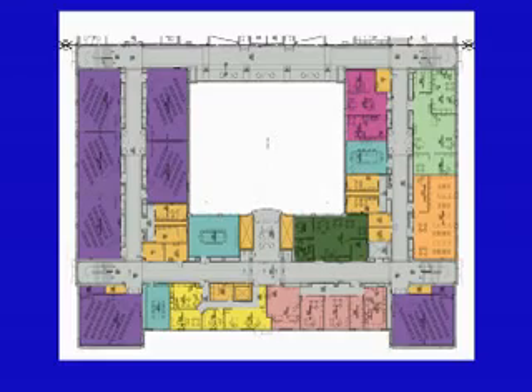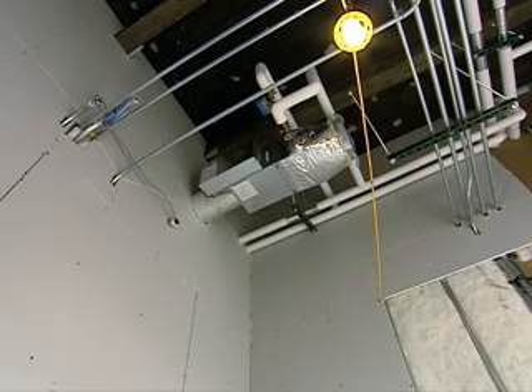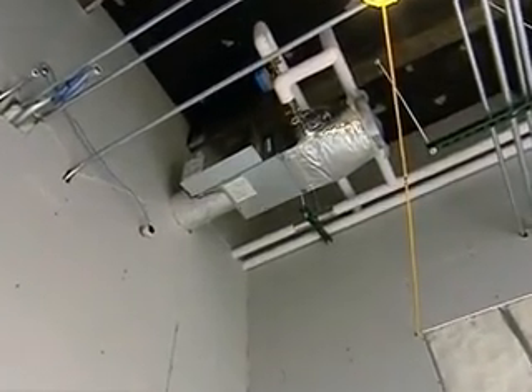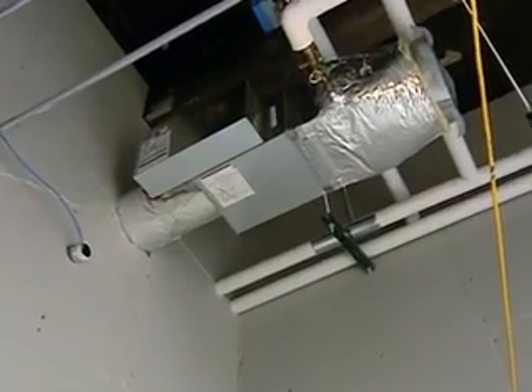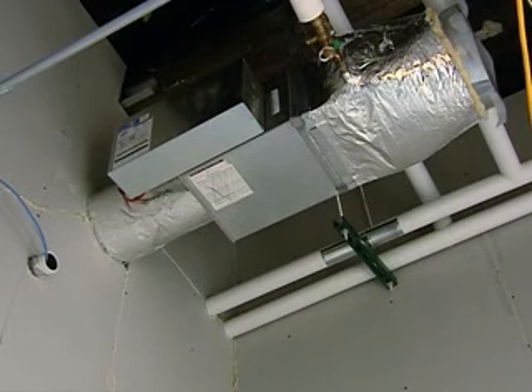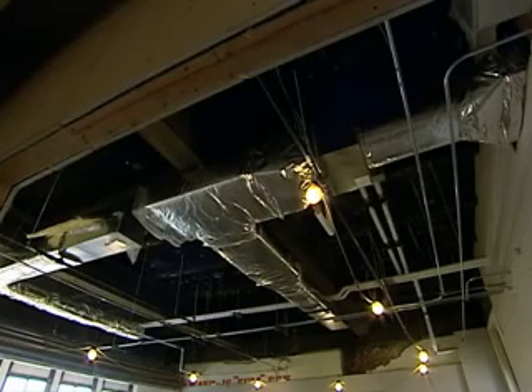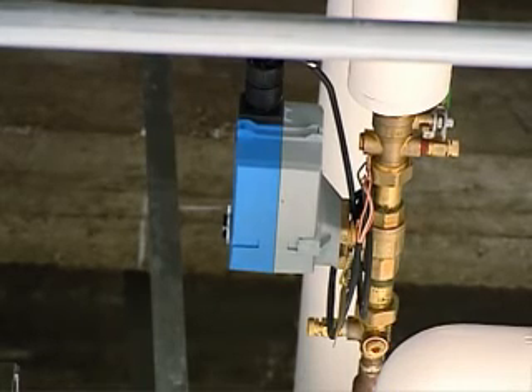The classrooms, the offices, almost every area is controlled by a VAV box, which allows you to control the temperature. We have a thermostat on the wall, so if someone likes it 65 degrees, they can achieve that, and if somebody likes it 80 degrees, they can achieve that. The VAV box is connected to our air handling systems that supply from our power plant, from our steam. It also supplies chilled water, and they blend those two together to get tempered air from what you've set on your thermostat. It's going to be one of the more comfortable places on campus once the bugs are worked out.